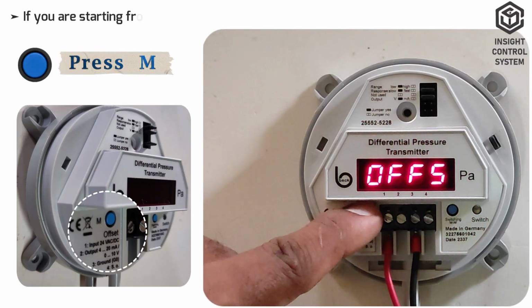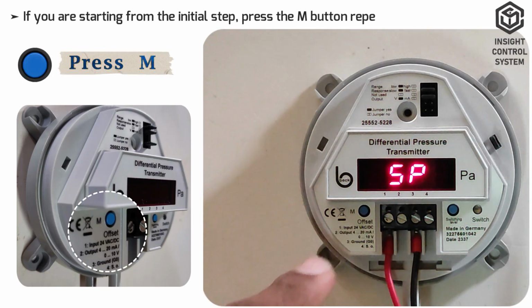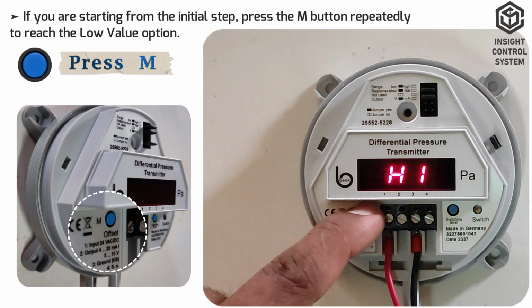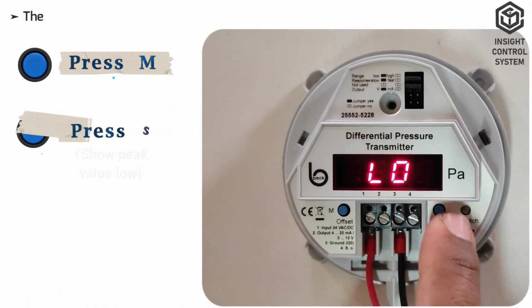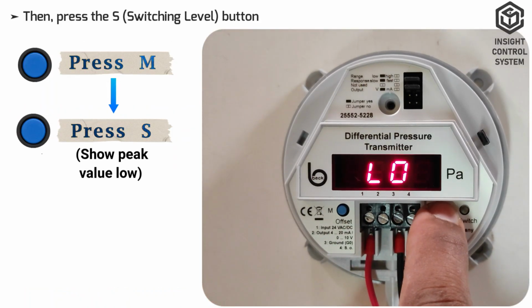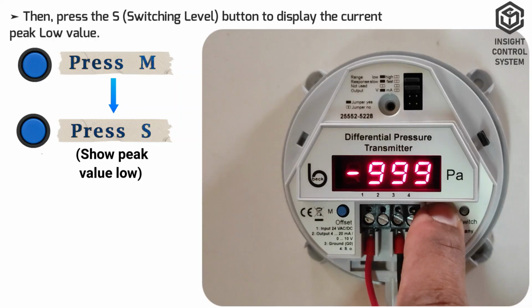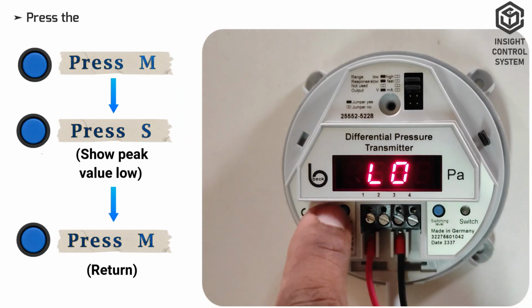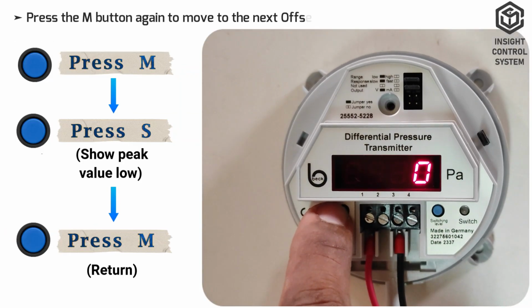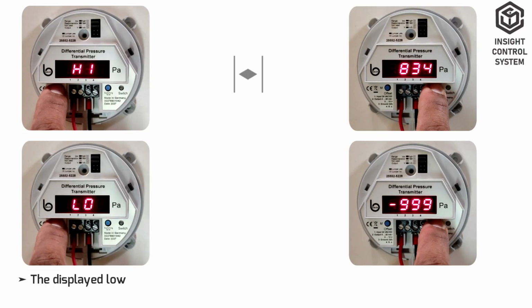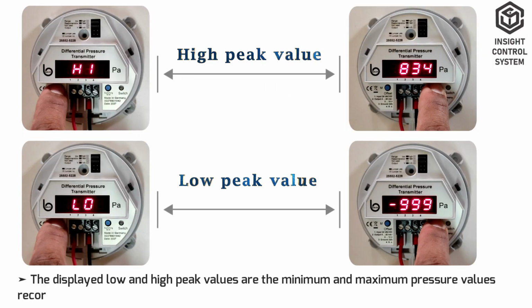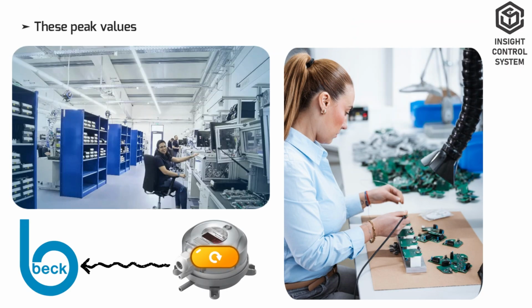Low value setting. If you are starting from the initial step, press the M button repeatedly to reach the low value option. Then press the S button to display the current peak low value. Press the M button again to move to the next offset option. The displayed low and high peak values are the minimum and maximum pressure values recorded by the sensor. These peak values can only be reset by the manufacturer.